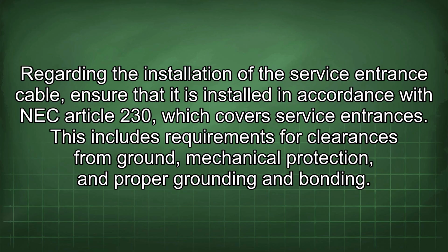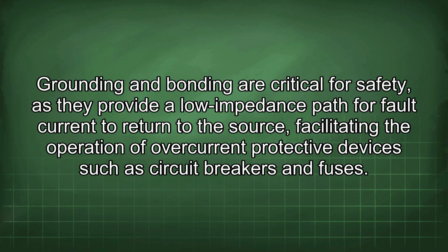Regarding the installation of the service entrance cable, ensure that it is installed in accordance with NEC Article 230, which covers service entrances. This includes requirements for clearances from ground, mechanical protection, and proper grounding and bonding. Grounding and bonding are critical for safety, as they provide a low impedance path for fault current to return to the source, facilitating the operation of overcurrent protective devices such as circuit breakers and fuses.